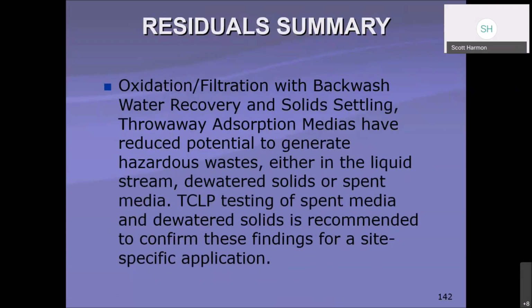So reduced potential to generate hazardous waste either in the liquid stream, dewatered solids, or spent media. TCLP testing of spent media and dewatering solids is recommended to confirm these findings for site-specific applications. And that's a biggie. You don't want to assume that that's the case. You want to make sure, by testing, that your findings are all in range, so you're not in that RCRA area where you need to meet those guidelines for toxicity.